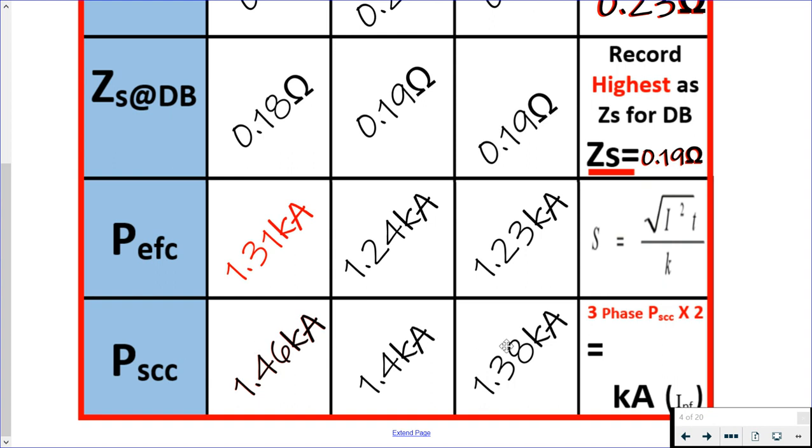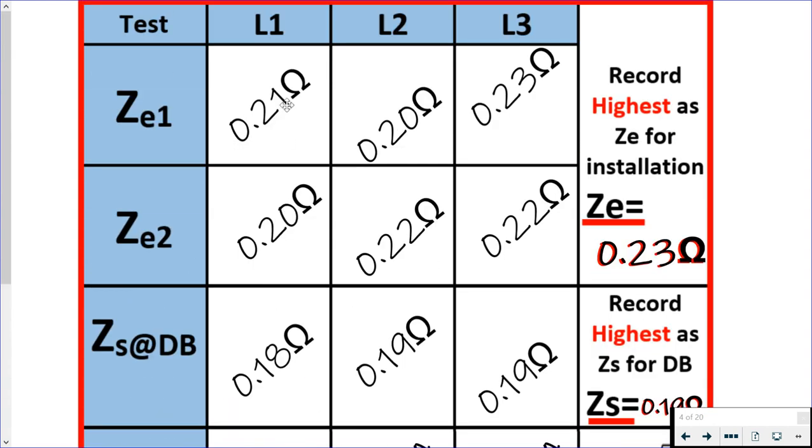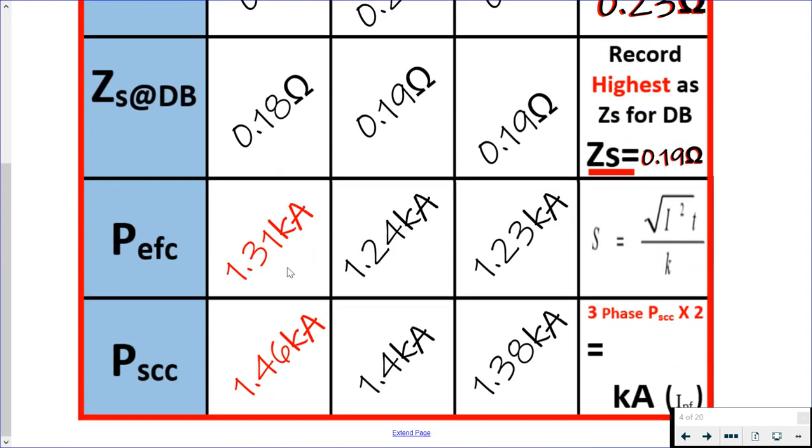Then we would carry out our prospective short circuit current: line one to neutral, line two to neutral, line three to neutral. The highest of which we then take is 1.46 kiloamps. Because it's a three phase system, we will multiply it by two. If this was just a single phase supply, I would be taking that 1.46 and recording it as my IPSC. When it's a three phase system, we take that 1.46 and we multiply it by two, giving us 2.92 kilo amps.